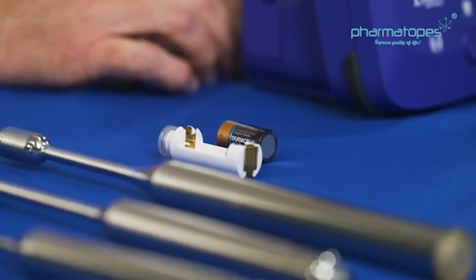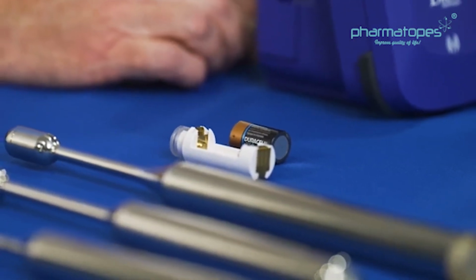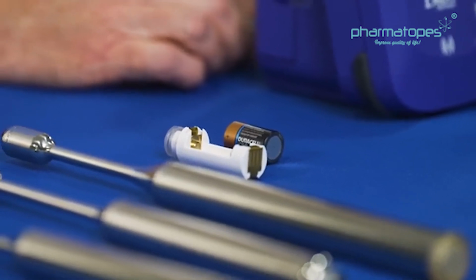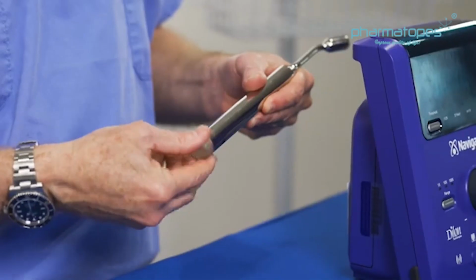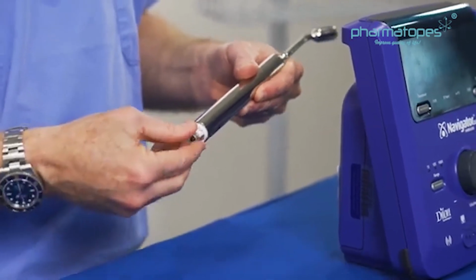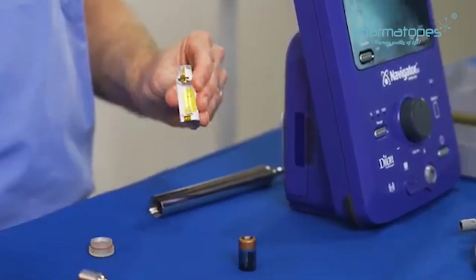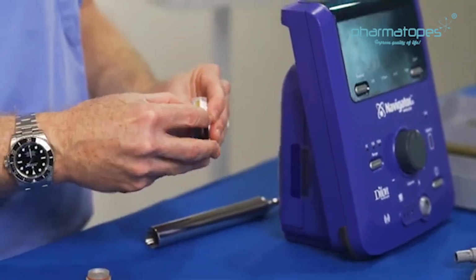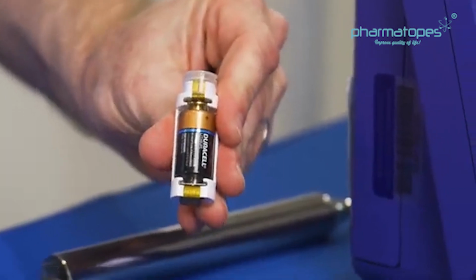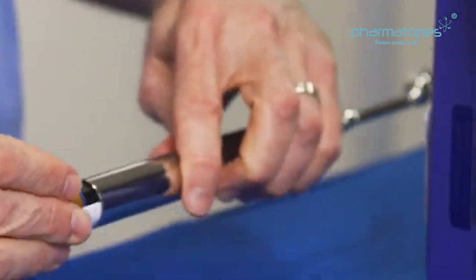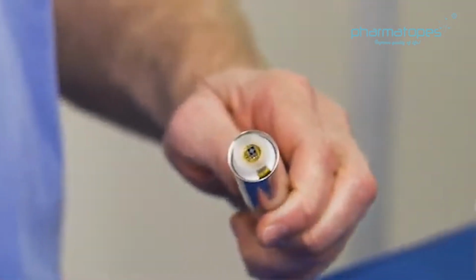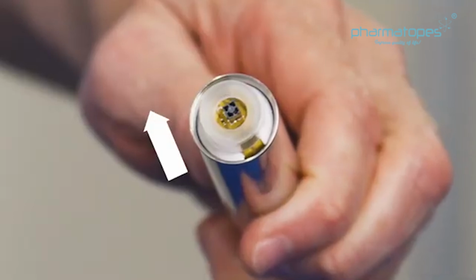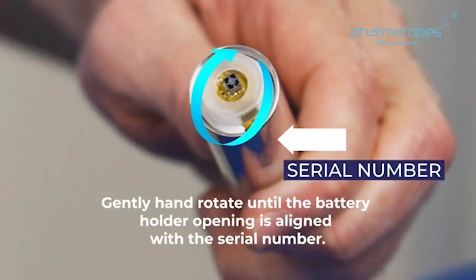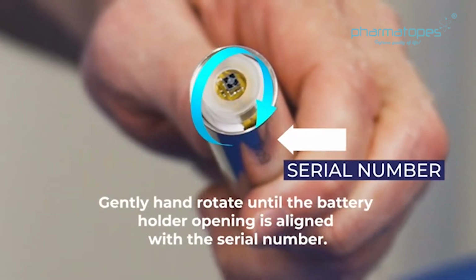A new battery is replaced by central processing after cleaning and prior to each sterilization. We will show the steps. Open the cap of the probe and remove the battery holder. Take a new battery and insert inside the battery holder with the plus next to this antenna. Insert the battery holder with the battery inside the probe with the antenna facing up and gently hand rotate until the holder opening is aligned with the serial number.